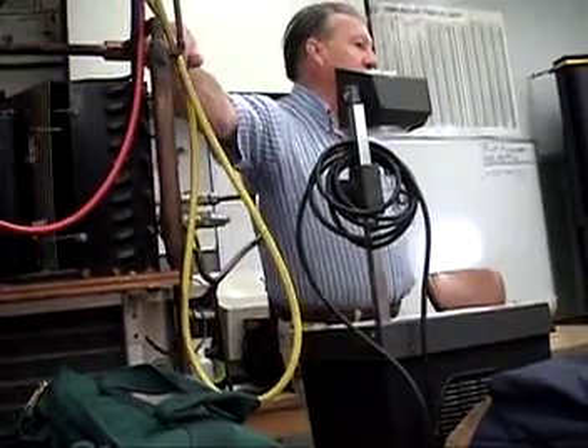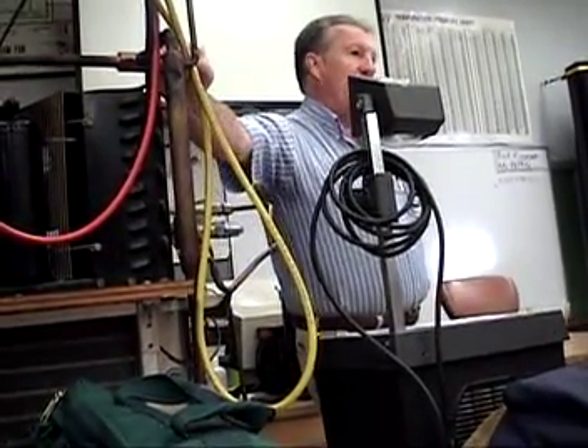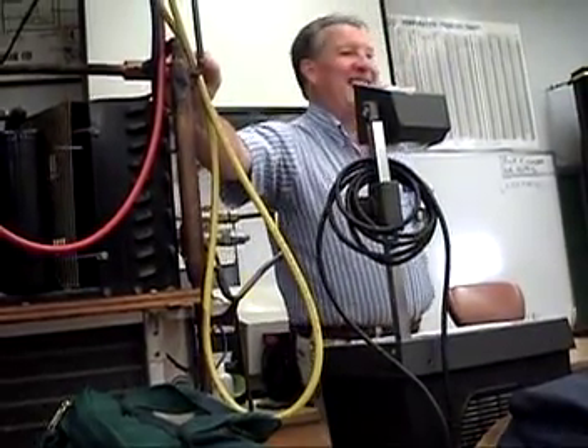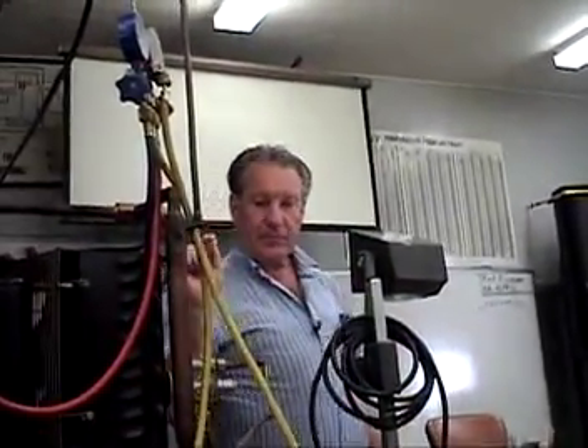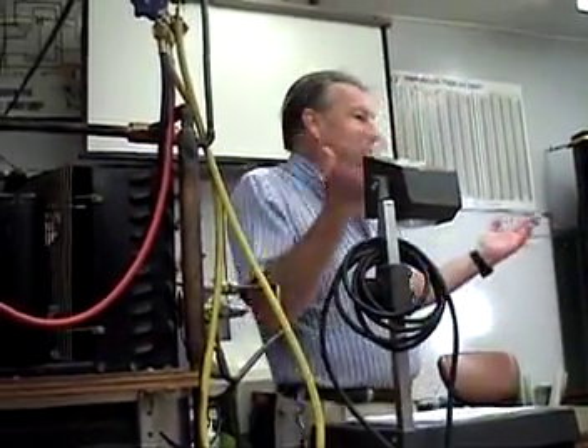Okay, but let's go back to the gurgling thing. If a refrigeration system is low on freon and you put your ear next to the metering device, what are you going to hear? You won't hear gurgling. What will you hear? Hissing. Exactly. Starving. Okay, so if it was low on freon, you would hear hissing instead of refrigerant going into the evaporator as a liquid. Refrigerant's going into the evaporator as a vapor because you just don't have enough refrigerant. So you'll hear hissing going into the evaporator.